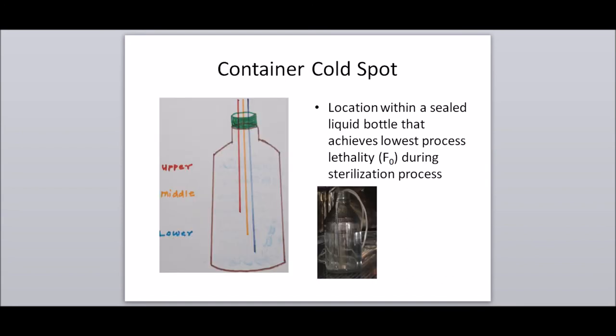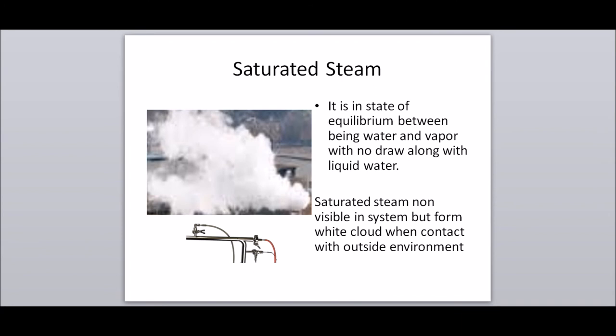Container cold spot: the location within a sealed liquid bottle that achieves the lowest process lethality, i.e., F0 value, during the sterilization process. Saturated steam: it is in a state of equilibrium between water and vapor with no liquid water. Saturated steam is non-visible in a system but forms a white cloud when it contacts the outside environment.